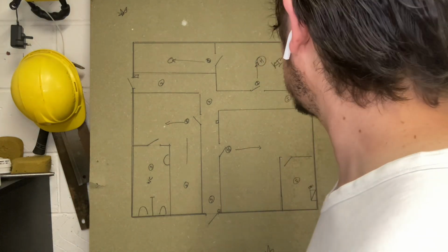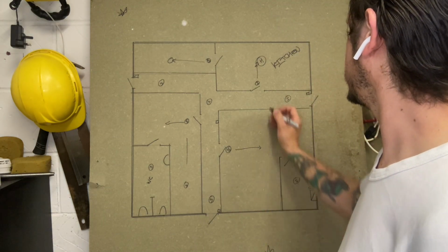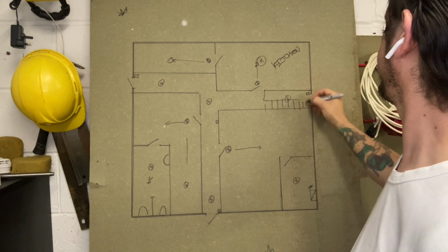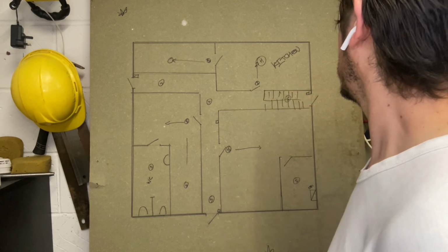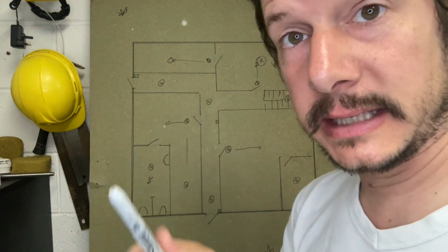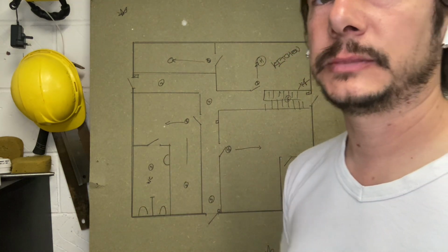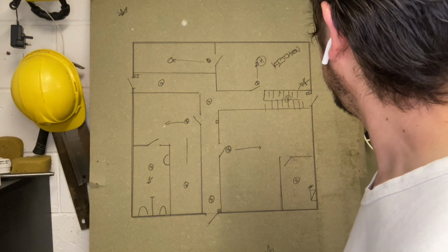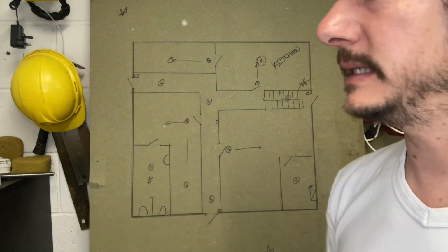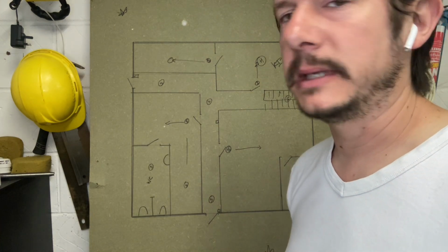A little bit about stairs. So where should we put a staircase in here? Let's have, this is now the stairs. And then you've got 4 floors of this. You would then have a detector on each landing, call point on each landing in a commercial environment. You may not need it on every one if you've got minimal ceiling heights and stuff. We're at 8 minutes, let's do a bit more.